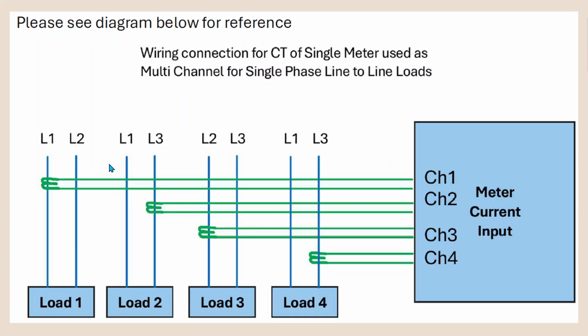It is possible to use different combinations. Here it's line 1, line 2. Here you can install also line 1, line 2. You can install any combination of phases for each channel. It is independently configurable which phases for each load. Later, we will show you how to configure each channel depending on the phases of each load.